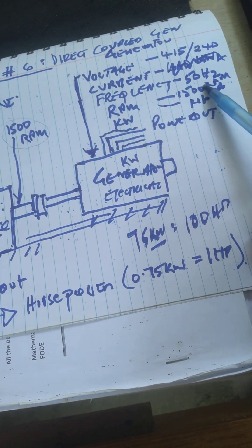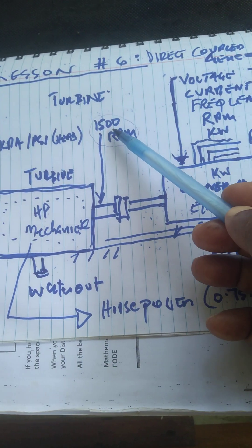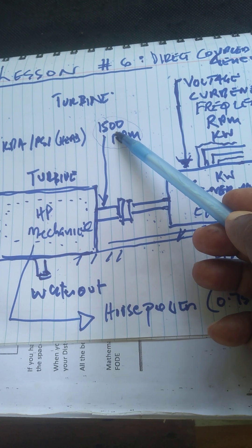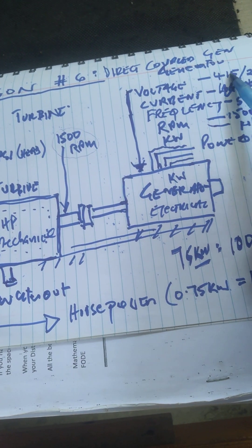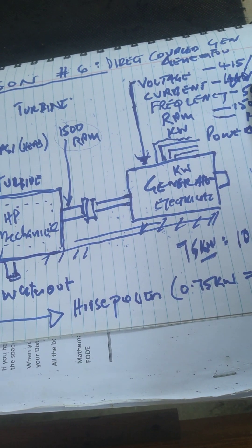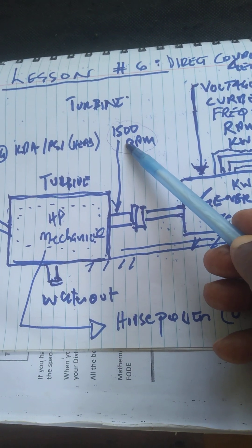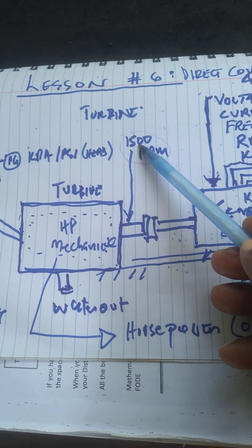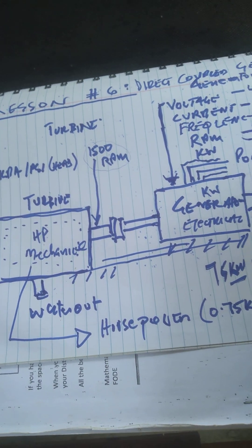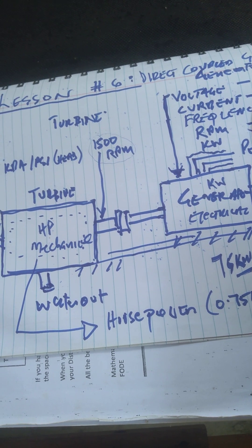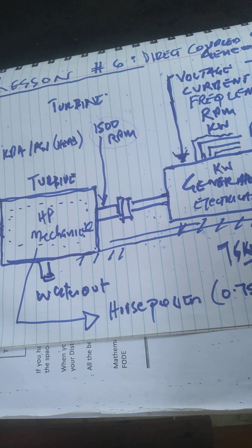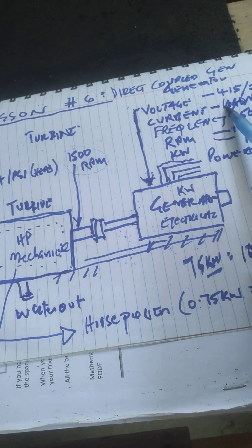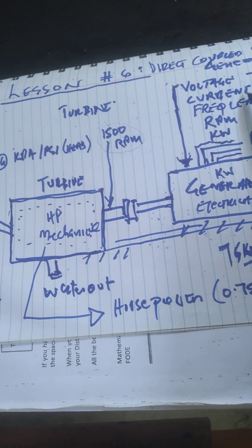If the speed is too low, you'll get low voltage and low frequency. Suppose it's 1600 RPM, you'll get high voltage, high frequency. This will damage all electrical equipment, so you really need to understand this.